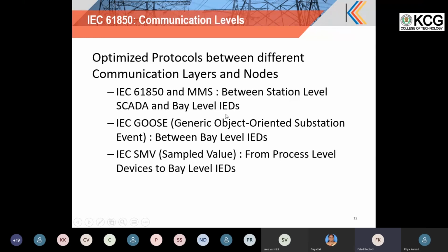And the inter-communication between multiple IEDs, or multiple equipment in the bay level, is carried out by a part of 61850 known as GOOSE, Generic Object Oriented Substation Events. This is directly mapped to the Ethernet interface without using the TCP/IP layers. So this is very fast, and the communication between multiple IEDs in a bay can happen in a fast mechanism. 3 to 4 milliseconds is what is recommended by the standard for communication.